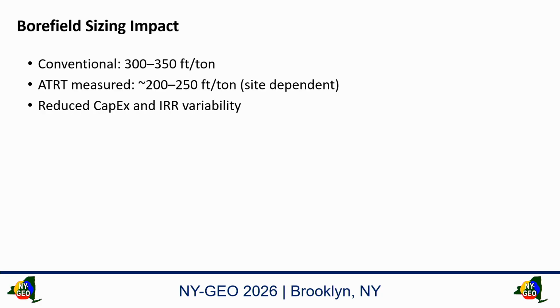On one project we would have been at 300 to 350 feet per ton. When we measure things right, we go to about 200 to 250 feet per ton. That's site dependent, not a rule of thumb, don't write that down. But I did reduce the capital expenditures and managed the internal rate of return variability. You see I'm headed to the finance guys now, right?